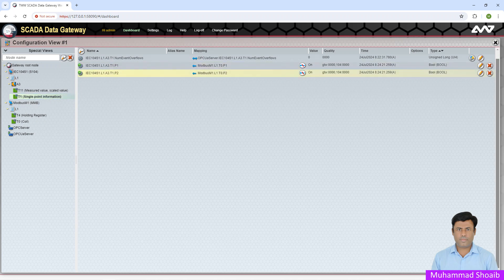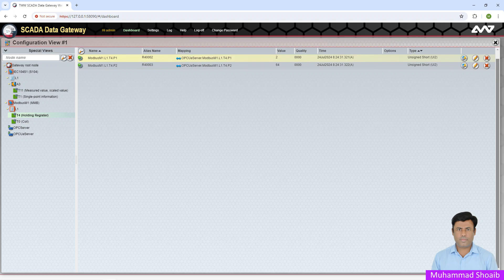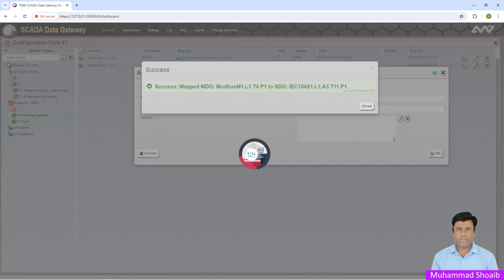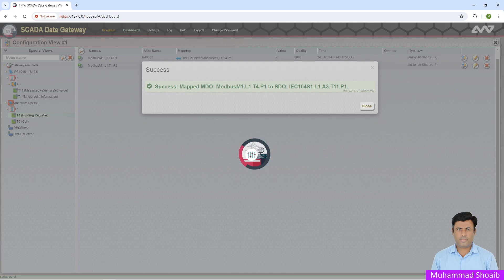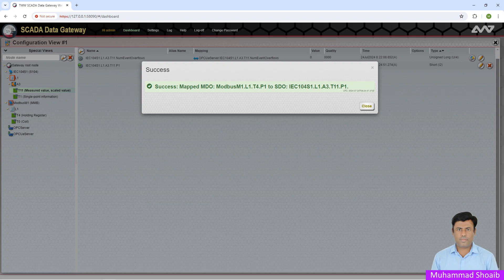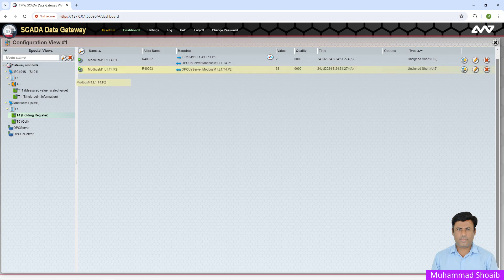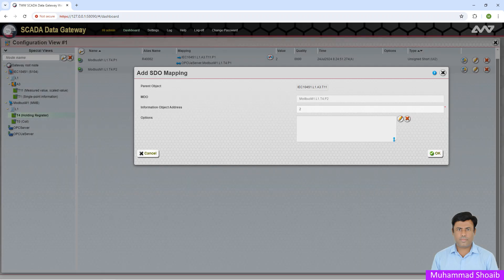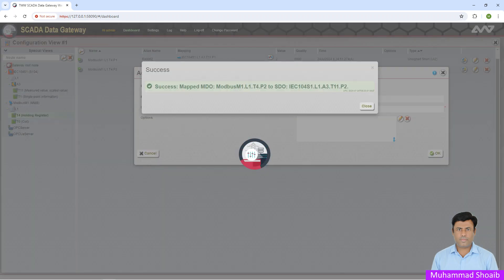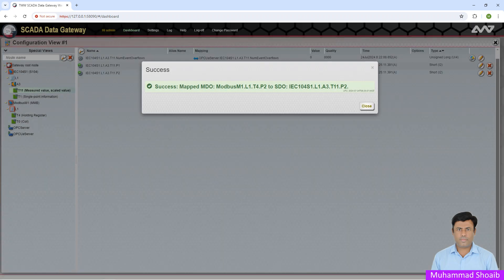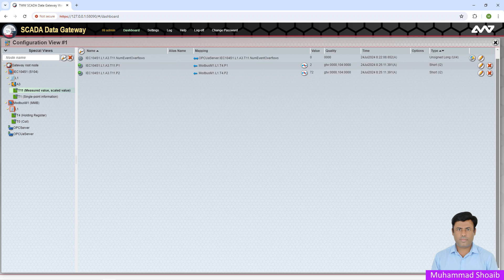You can see these two tags are successfully mapped. Now go to the holding register — select the tag and drop it over the Measured Value. Select the same tag and press OK. The mapping between master data object and slave data object is successfully completed. Click Close, then go to the second tag, drag and drop it, and press OK. That's it for the SCADA Data Gateway site configuration.